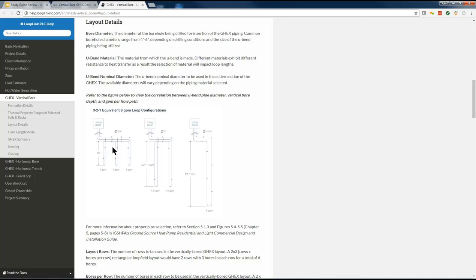Okay, so you can see this is a 3-ton example shown in the drawing here. So 3 loops, a 3-ton loop field, 1 loop per ton. Translating that to a larger pipe size, generally with 1-inch pipes, you want each loop to represent 1.5 tons. So notice that the depth for these 1-inch counterparts is 1.5 times deeper than the 1-ton option in the 3/4 inch, and the flow rate is 4.5 GPM, which represents 1.5 tons of capacity.